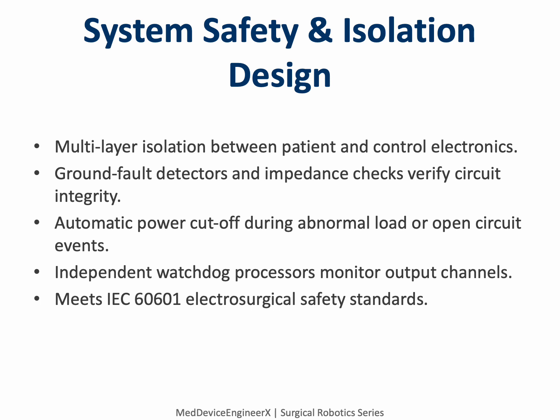Every component complies with IEC 60601 and IEC 60601-2-2 standards for electrosurgical safety, including leakage current and insulation thresholds. This architecture ensures that while the system manipulates high energy levels, the patient remains electrically isolated and the surgeon remains in control at all times.